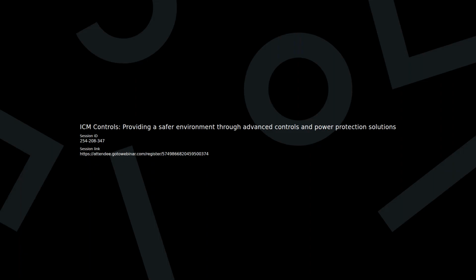The next question I have is, what does a standard surge protection device protect against? A standard surge protection device protects you against surges caused by lightning, also power grid failures where you've got power going on and off, transformers acting bad, downed power lines, anything that can cause fast acting transient spikes. Big pieces of equipment turning on and off can create those spikes as well. These days, dirty power is a very general term. I hate to use it, but most people understand what dirty power is: power with a lot of fluctuations, a lot of surges, just bad power. We're getting a lot of that with the overuse of our outdated grid service right now, so it's becoming a requirement in many cases. That's why you need it.